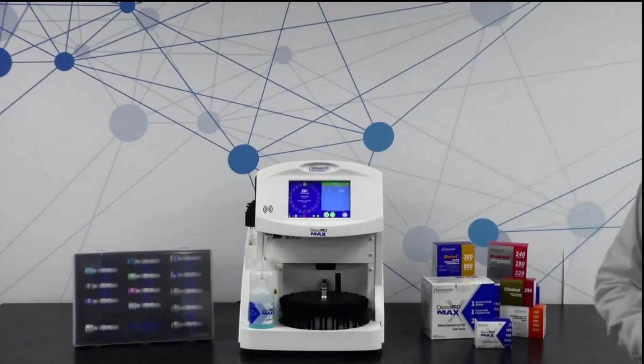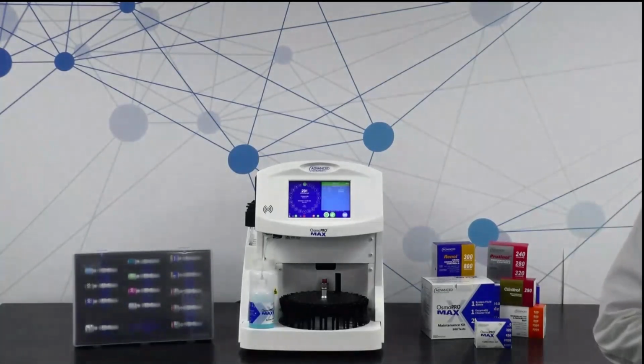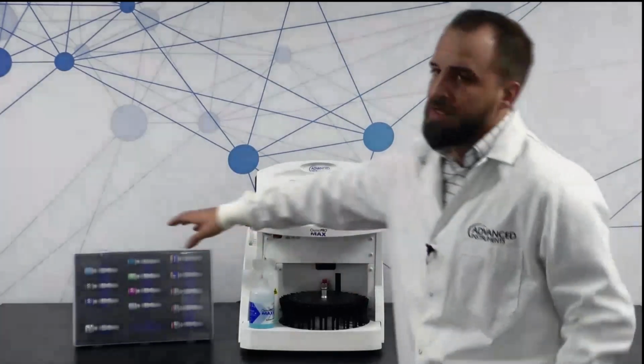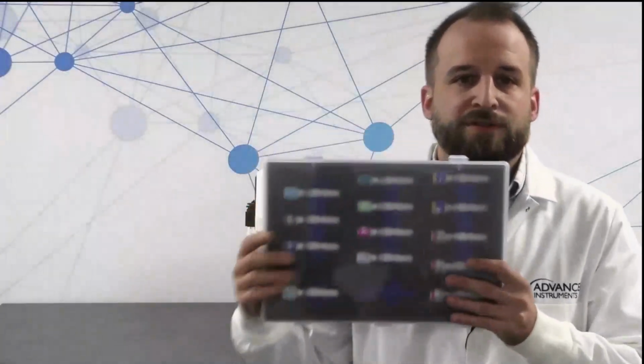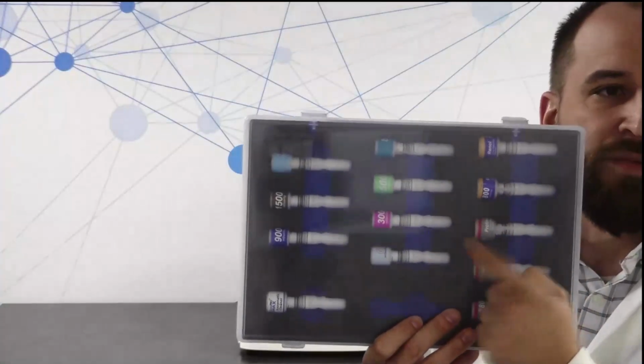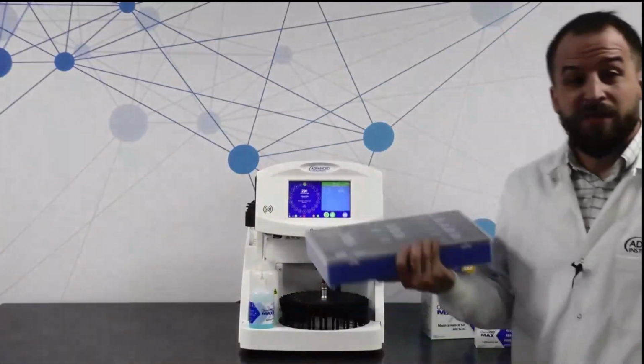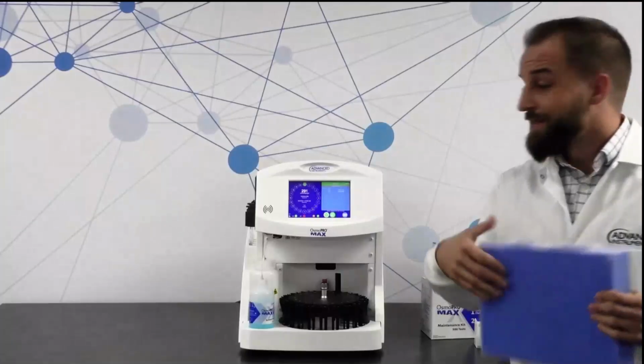What's great about that is the calibration process is fully automated on board the OsmoPRO MAX. I can show you a little bit about what that looks like later on as well, but there's no more standing in front of your instrument, pipetting your sample, loading it into your Osmo One, getting your result, doing that 3 times for every level and just standing there the whole time. With this one, you can utilize these great ampule adapters to ensure that you are putting the ampule for whatever calibration standard it is that you're running through your calibration protocol, and then loading them up per instructions that are actually going to be available to you in the software on board, and then hitting start and walking away.